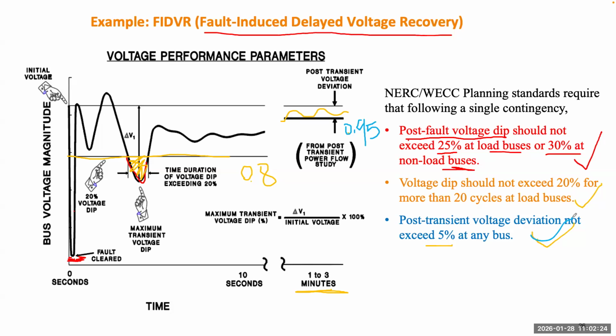In order to check this criterion, the engineer has to simulate each individual single contingency, especially for those close to motor loads. So this is one example. Even if the system never loses stability, we still need to do a dynamic study to know the actual response. We will come back to this criterion in the voltage modeling and regulation section. We will talk about how we can mitigate this problem.